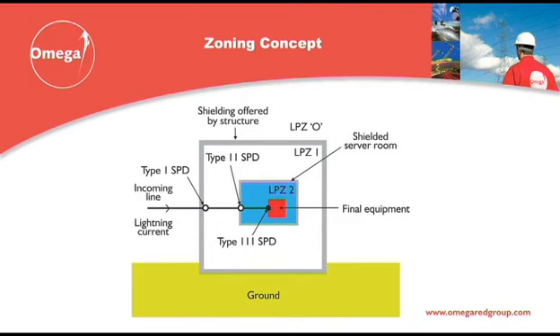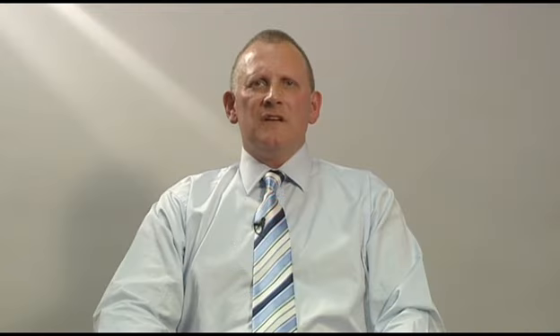Coordination with equipment manufacturers is necessary, as they should have the technical data to allow the lightning protection specialist to determine the various levels of protection required at the boundary of each zone. The different risks associated with R2, risk of loss of service to the public, are addressed in different ways.